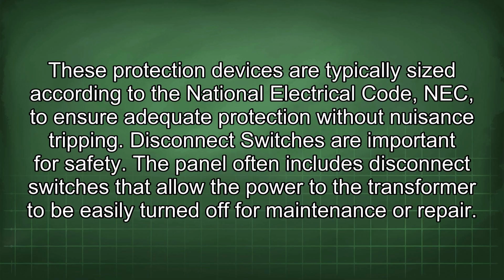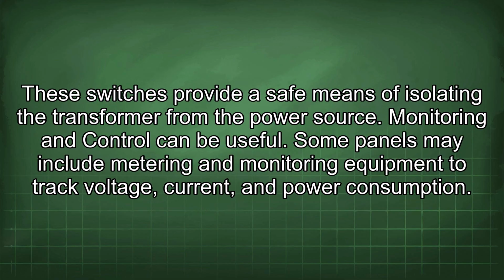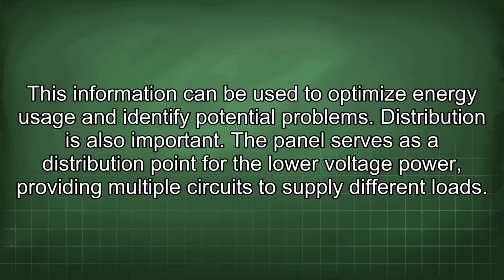Disconnect switches are important for safety. The panel often includes disconnect switches that allow the power to the transformer to be easily turned off for maintenance or repair. These switches provide a safe means of isolating the transformer from the power source. Monitoring and control can be useful. Some panels may include metering and monitoring equipment to track voltage, current, and power consumption. This information can be used to optimize energy usage and identify potential problems.